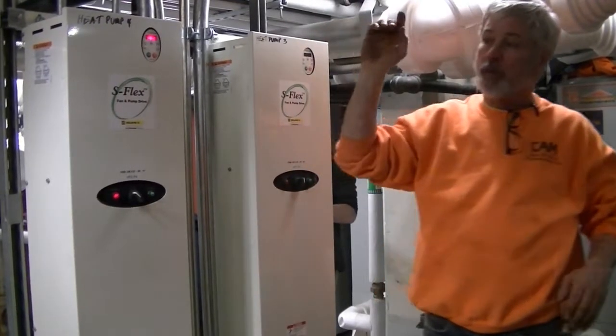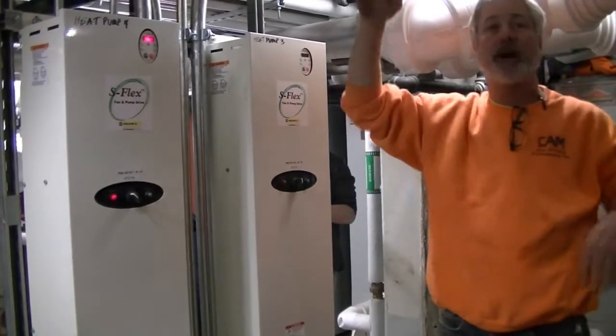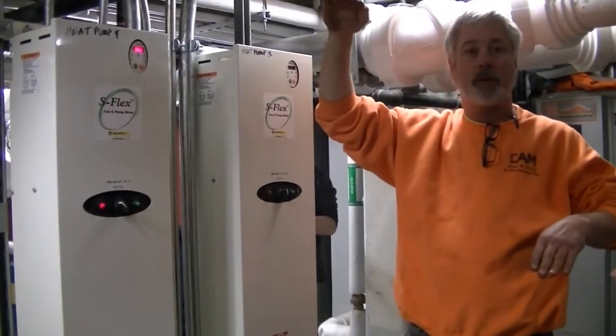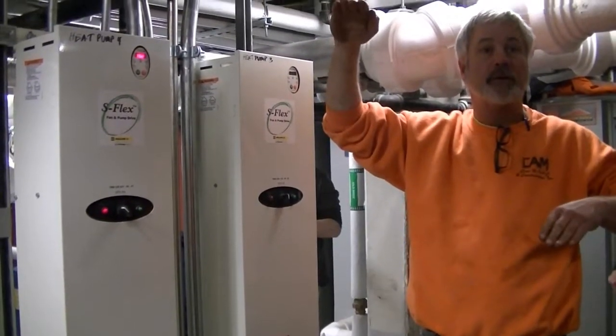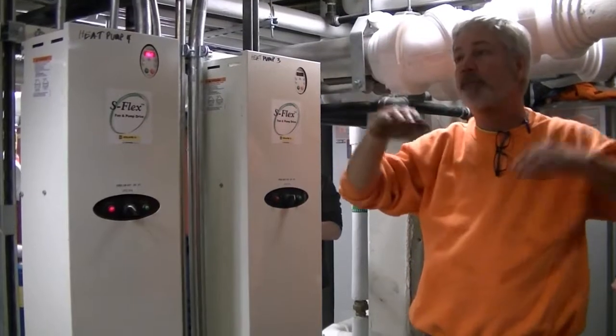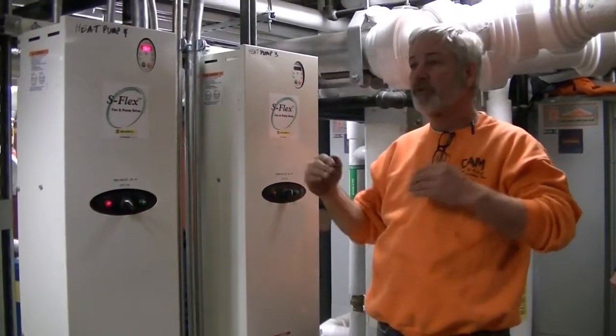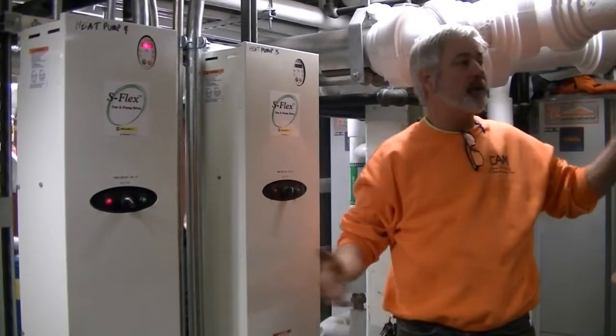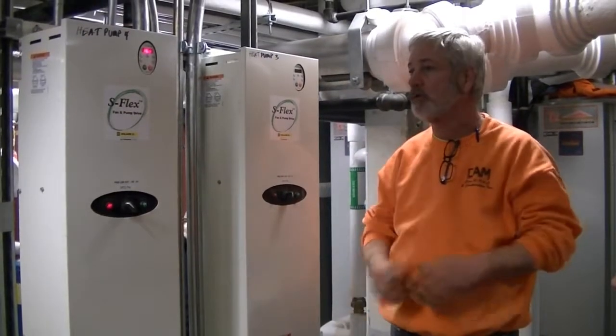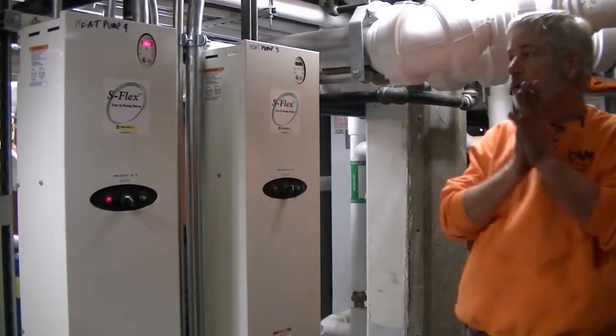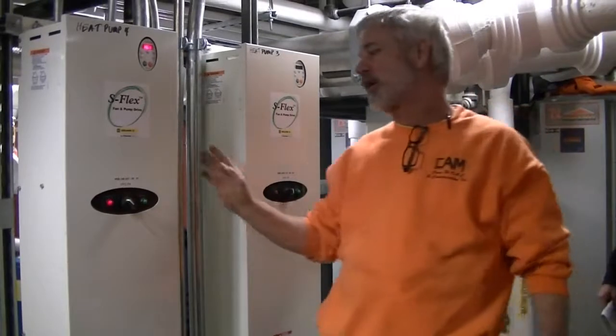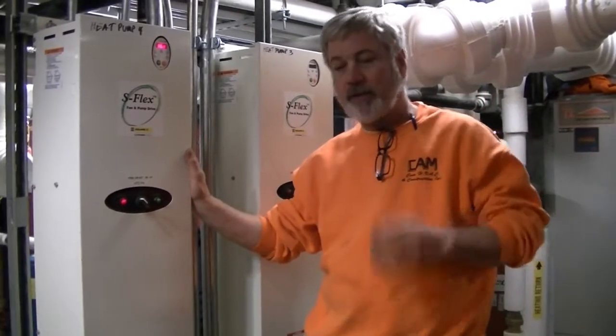What our differential sensor does is says we've got too much water flow. This piping's starting to get restricted. So they start slowing the pump down so we can maintain the same amount of water flow no matter how many valves are open and how many valves are closed. And there are a couple of things that you cannot adjust on these that are factory set.